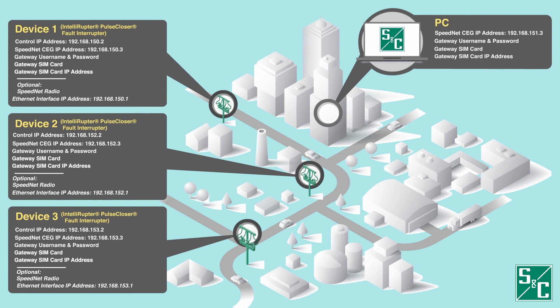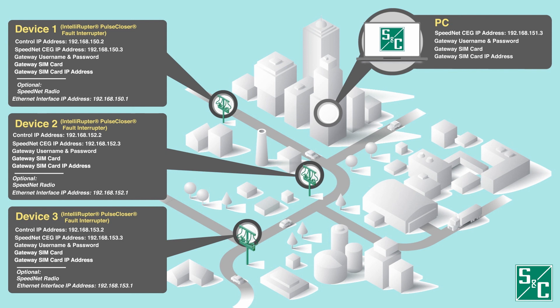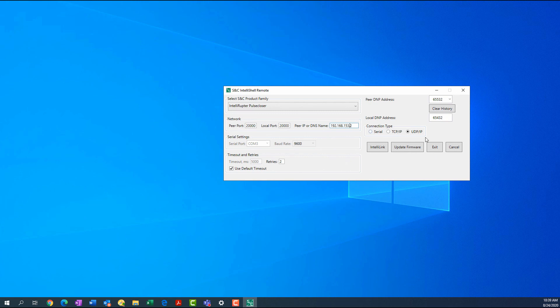To do this, we'll use the PC. Confirmation that each IntelliRupter fault interrupter is capable of communicating over the cellular network is provided by establishing a remote connection to the IntelliRupter fault interrupter through S&C IntelliLink. This will require that the PC has persistent Internet Protocol Version 4 routes capable of directing traffic to the IP addresses of the IntelliRupter fault interrupter controls. These can be added by using the PC's command prompt. To make the remote connection, use the IP address that was assigned to the IntelliRupter fault interrupter control.